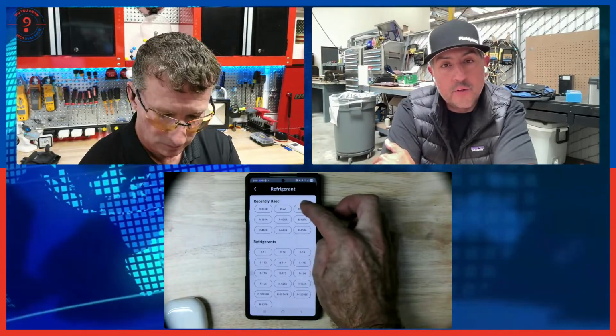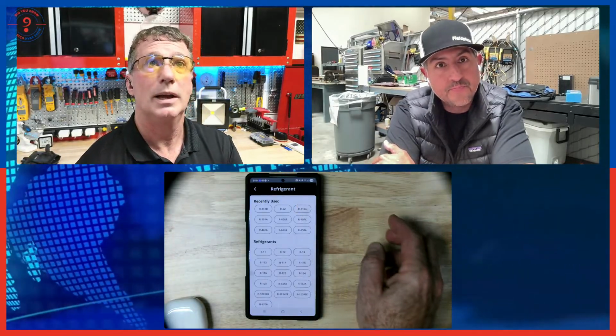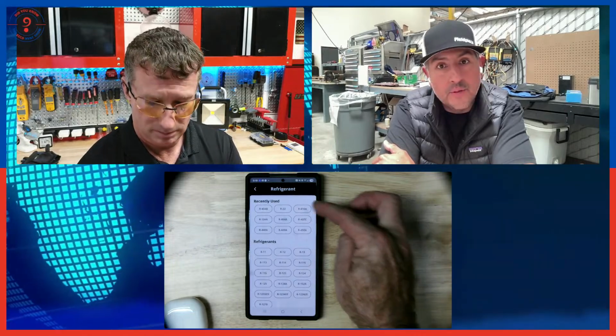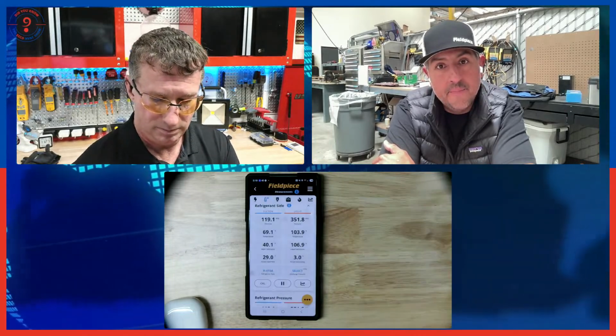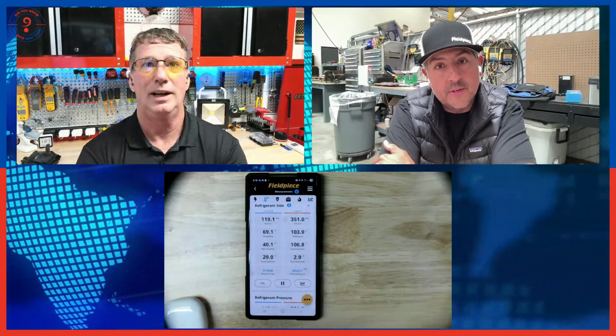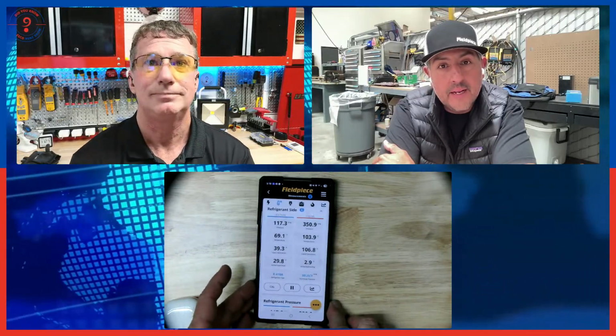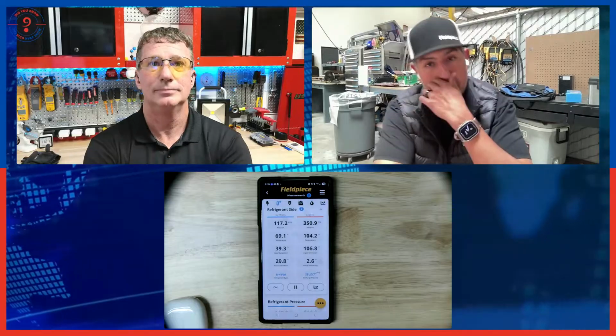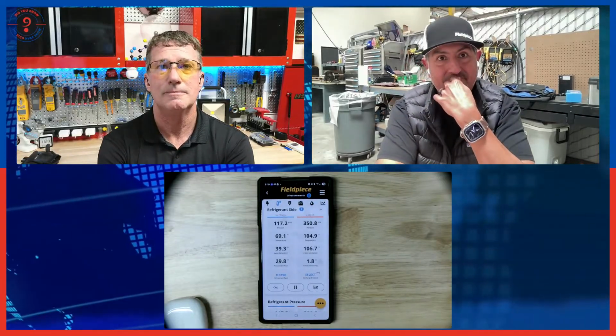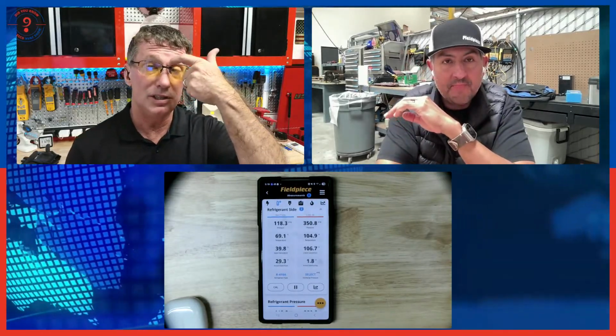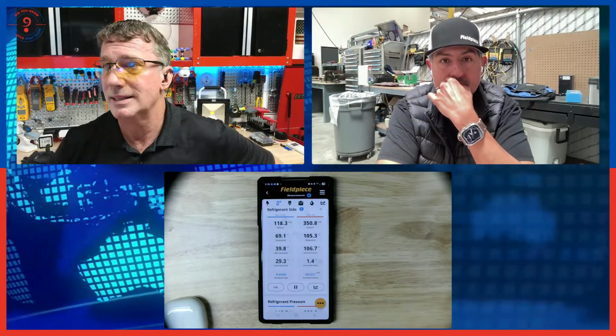So what refrigerant type is your system, Clifton? This is an R410A unit. R410A. So we're going to select R410A. And now you'll see we populate saturations. And we got superheat on the left and subcooling on the right. Okay. Very intriguing. So now it just started, so we'll give it a few minutes to balance out.